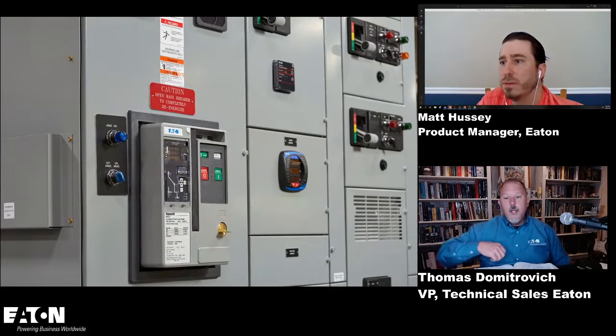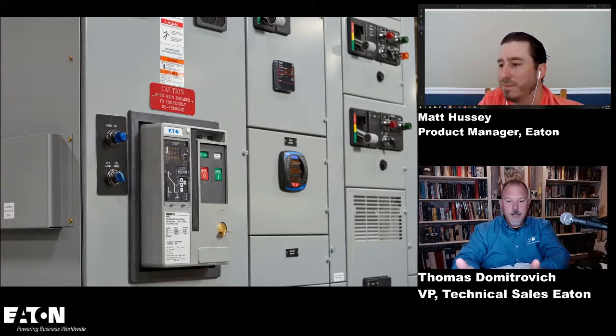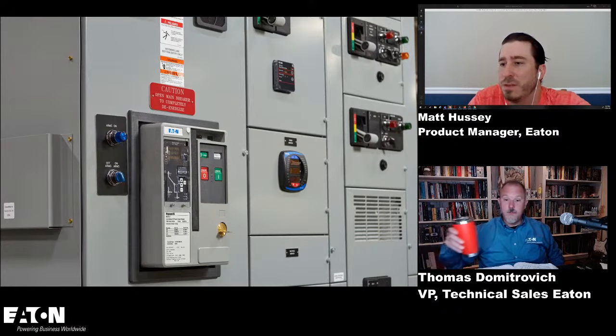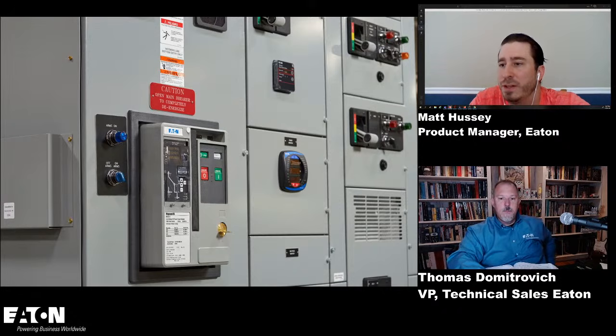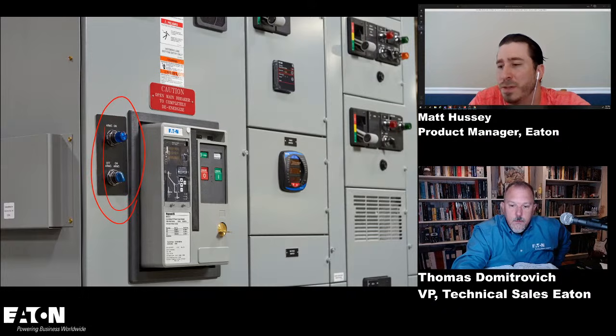Excellent. All right, so now as we move on, I'm looking at this motor control center. When I first saw this picture, I was like, that's not a motor control center. I got a Magnum circuit breaker there. That's a power circuit breaker. You don't find power circuit breakers in motor control centers. And Matt, you said, yes, you do. Of course. I think a lot of industry applications utilize it. There's a lot of capabilities there, from electrical operation of breakers. Looks like we got some energy reducing maintenance switches there. Looks like they've also got a Kirk lock on this one, so they might be doing a main application with maybe a generator feed on the other one.